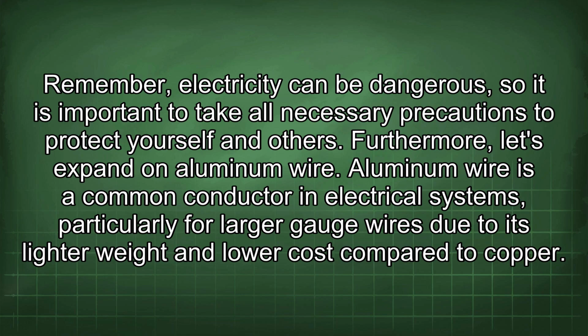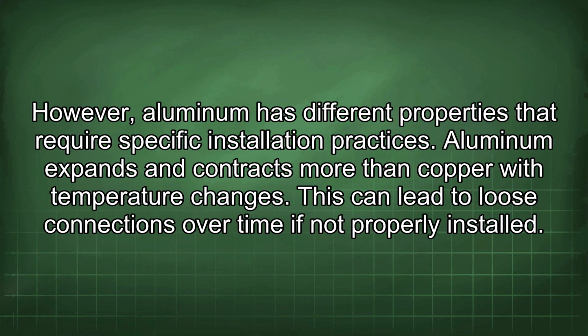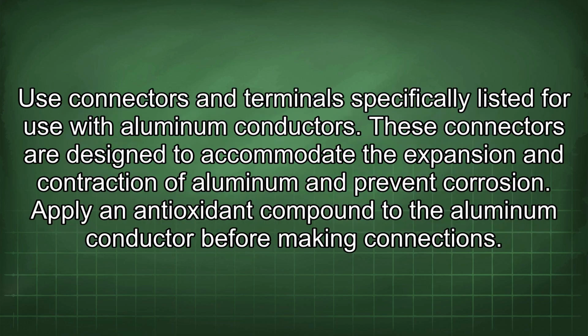Furthermore, let's expand on aluminum wire. Aluminum wire is a common conductor in electrical systems, particularly for larger gauge wires due to its lighter weight and lower cost compared to copper. However, aluminum has different properties that require specific installation practices. Aluminum expands and contracts more than copper with temperature changes. This can lead to loose connections over time if not properly installed. Use connectors and terminals specifically listed for use with aluminum conductors. These connectors are designed to accommodate the expansion and contraction of aluminum and prevent corrosion.